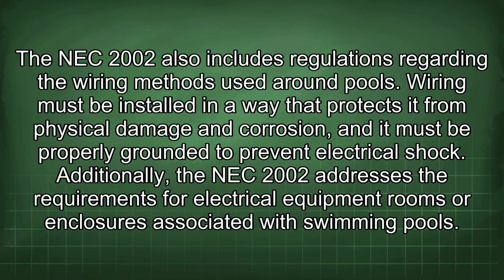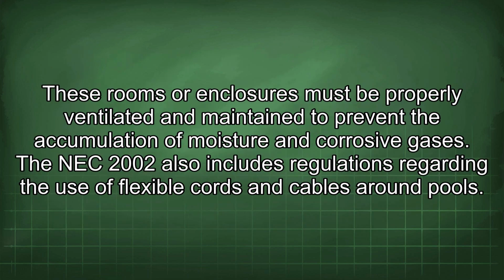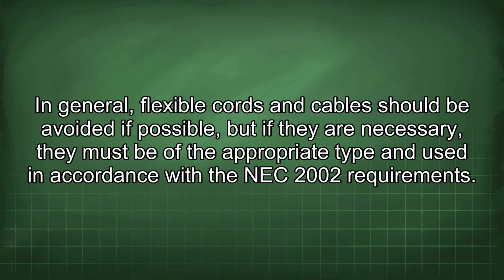Additionally, the NEC 2002 addresses the requirements for electrical equipment rooms or enclosures associated with swimming pools. These rooms or enclosures must be properly ventilated and maintained to prevent the accumulation of moisture and corrosive gases. The NEC 2002 also includes regulations regarding the use of flexible cords and cables around pools. In general, flexible cords and cables should be avoided if possible, but if they are necessary, they must be of the appropriate type and used in accordance with the NEC 2002 requirements.